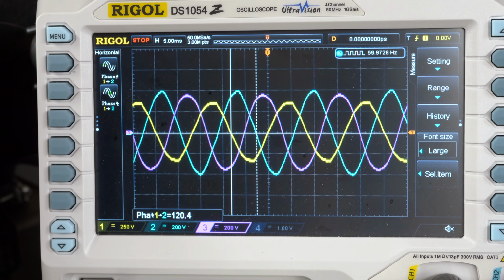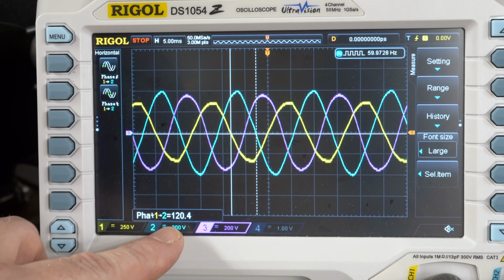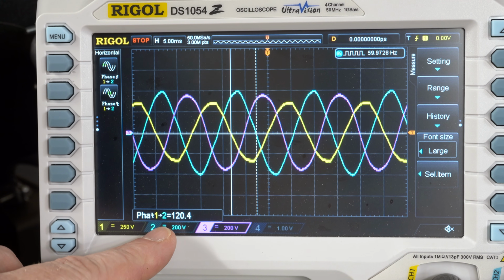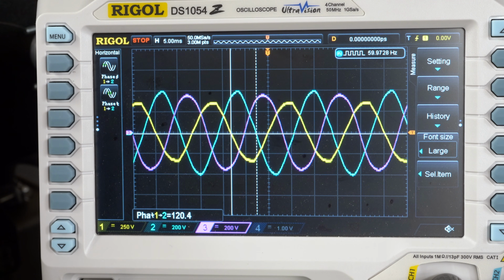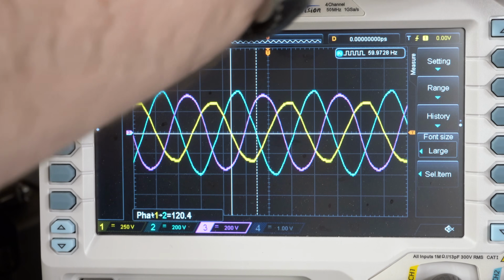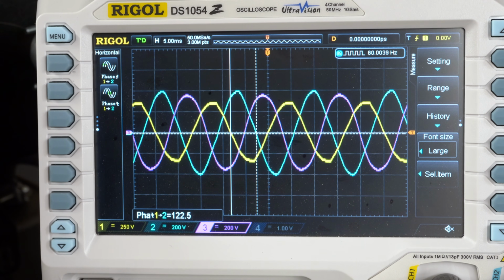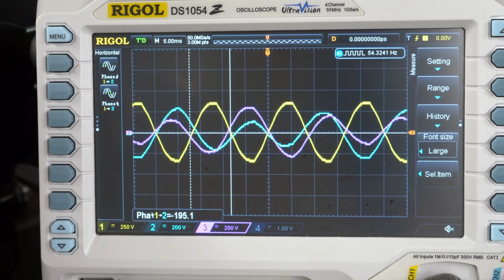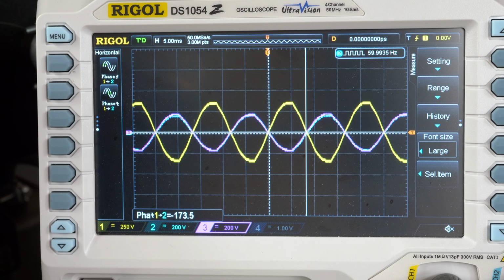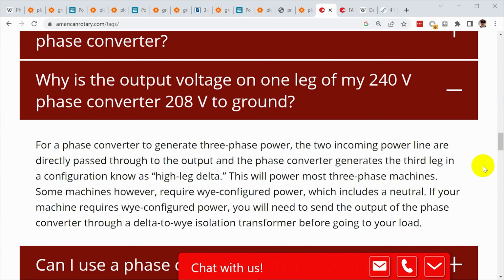We can see here that the phase angle between 1 and 2 is measured at 120.4 degrees. Now, if we just let this free run, it does jump around a little bit because this particular scope is having a little bit of trouble locating the zero crossings, but what it's measuring is close enough to convince me that it's correct. There has been enough confusion about this topic that American Rotary actually addresses it in their FAQ.